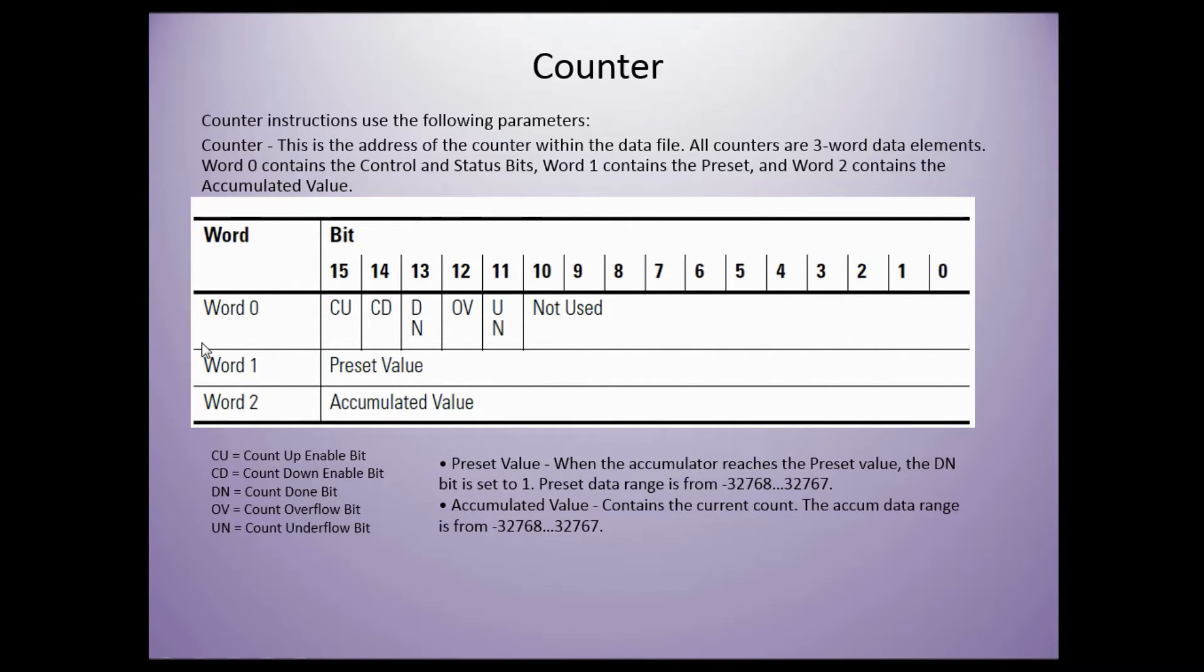Counter instructions use the following parameters. The counter is the address of the counter within the data file. All counters are three word data elements. Word zero contains the control and status bits. Word one contains the preset and word two contains the accumulated value.